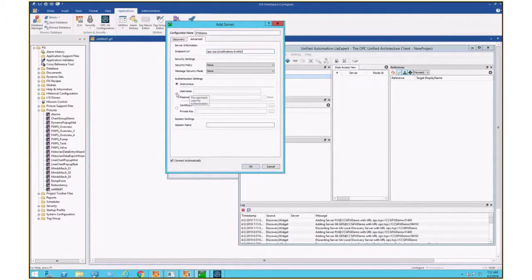Also, the other aspect of OPC UA is that you have the ability to require authentication. So iFix has kind of two modes. One, you can start out with no security configured, which we respect, in which case you would be able to connect anonymously to it. Or, and often recommended, is setting up security on iFix and requiring connections to authenticate with iFix users. So in this case, I'll give my credentials so that I can log in. So then it tries to connect.